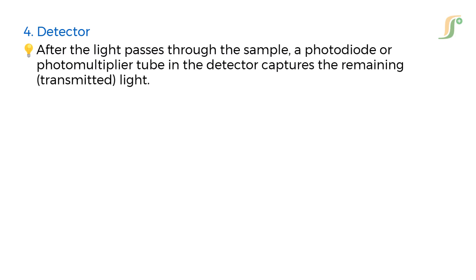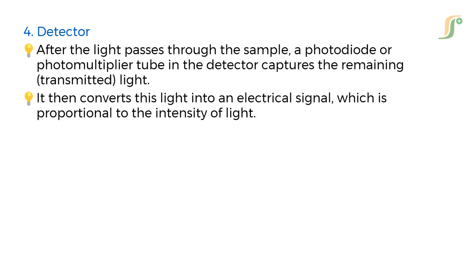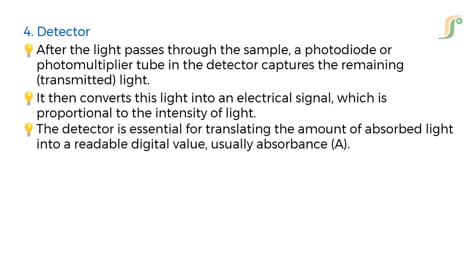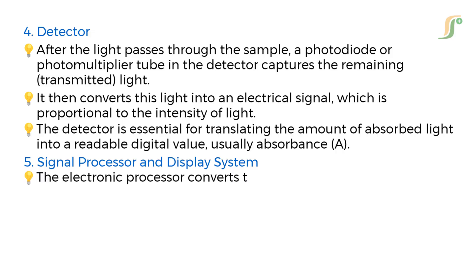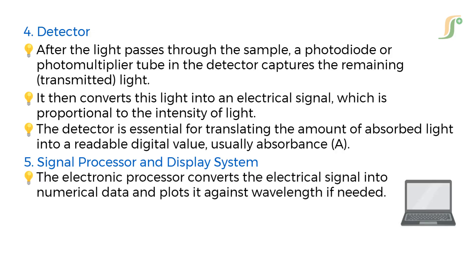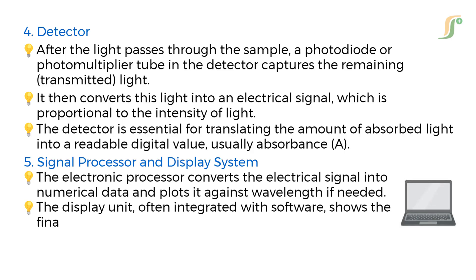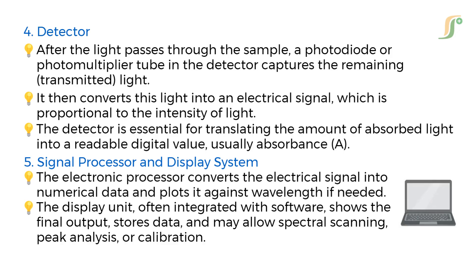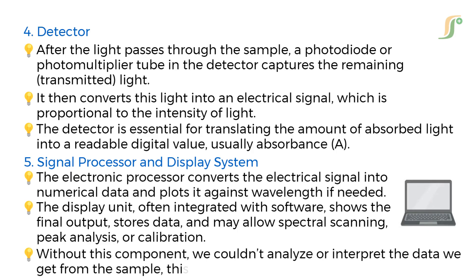After the light passes through the sample, a photodiode or photomultiplier tube in the detector captures the remaining transmitted light. It then converts this light into an electrical signal, which is proportional to the intensity of light. The detector is essential for translating the amount of absorbed light into a readable digital value, usually absorbance. The electronic signal processor converts the electrical signal into numerical data like absorbance or transmittance and plots it against wavelength if needed. The display unit, often integrated with software, shows the final output, stores data, and may allow spectral scanning, peak analysis, or calibration. This is where science meets usability.